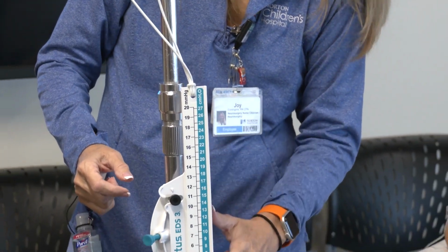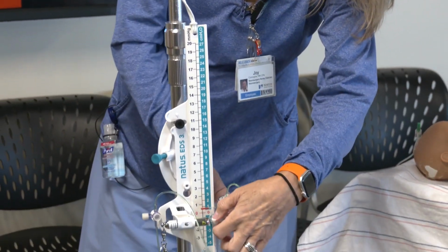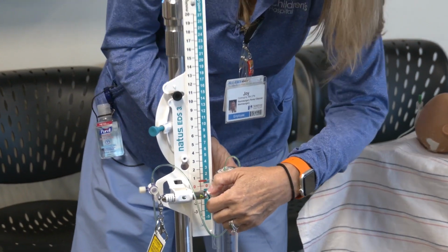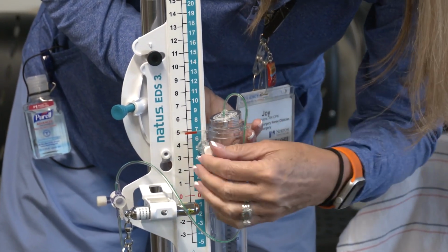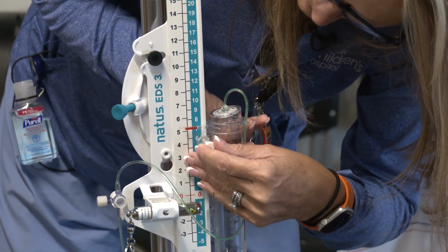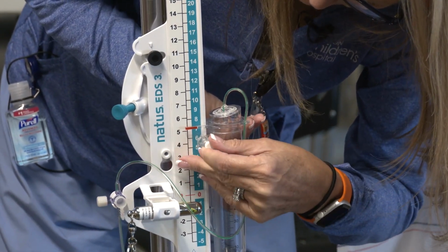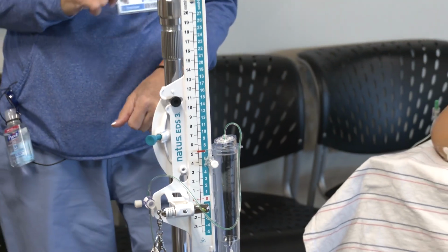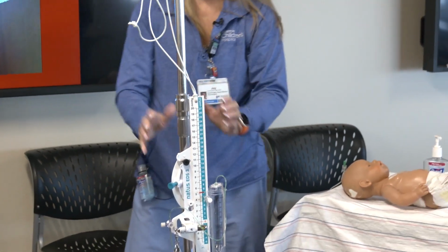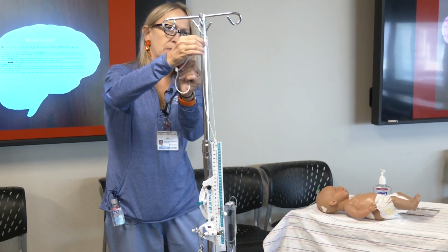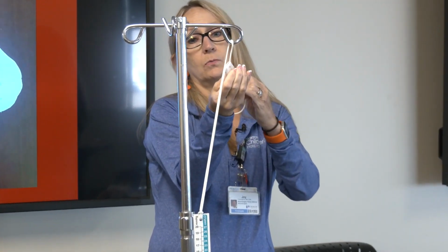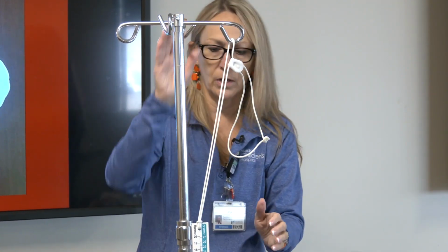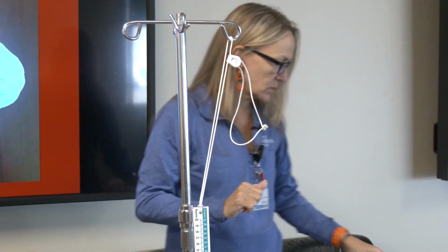So you're going to be using this gauge over here. You're going to loosen this white screw, and you are going to, using the green numbers, put that red little mark over the top at eye level at the 7 centimeters of water. Okay, so that's the pressure number. Now that I had this all set up, I do need to take the slack up in this cord, because if somebody tightened it too much and it fell, you want it to be relatively hanging where it should be. So that's with the cord taken up now.